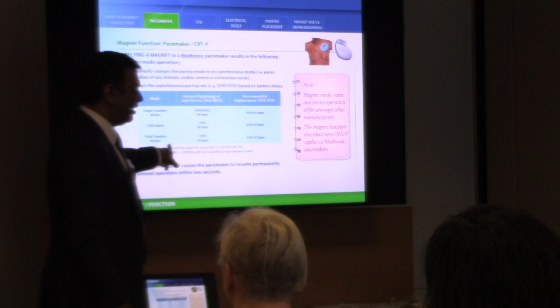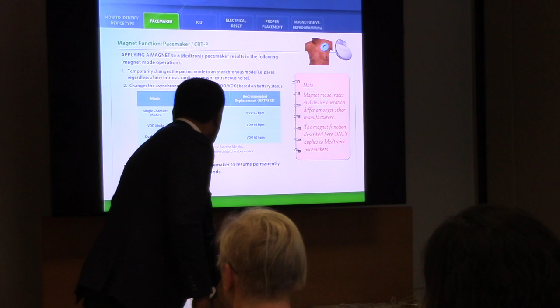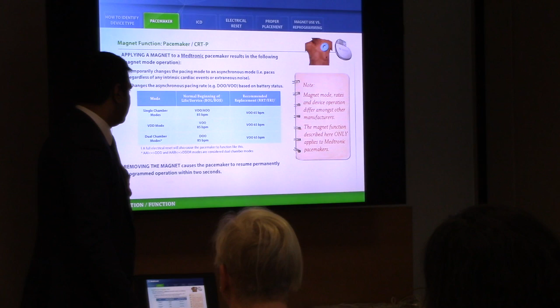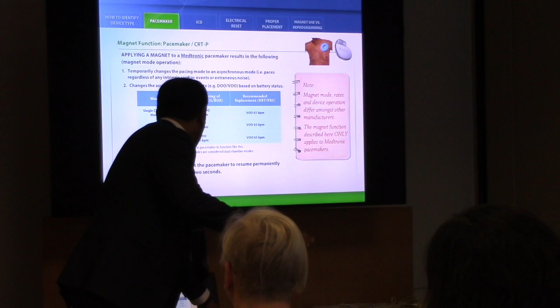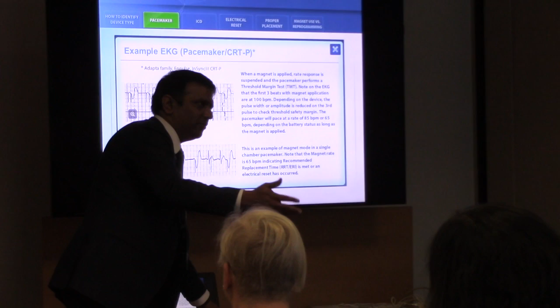And you have the dual chamber. If they have a dual chamber pacemaker, it's going to go DOO, right? And removing the magnet will cause it to resume permanently programmed operation within 2 seconds. Once you take it off, it will go back to whatever it's programmed to, so you don't have to ask us to come check the device unless you think there's an issue while they did the surgery.